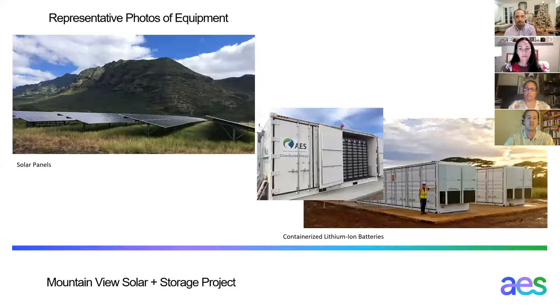I'll talk a bit more about this, because it's been a concern raised by community members. The containers include a built-in fire suppression system, so if there were an event with one of the batteries, this system would automatically kick in and contain it within the unit. The batteries are mounted on concrete pads, and each pad is surrounded by a non-vegetated fire break, usually gravel. This photo was taken during construction, which is why it's dirt there, but gravel or non-combustible material would surround all the pads as another layer of fire protection.